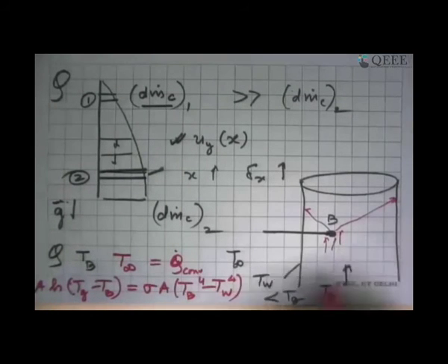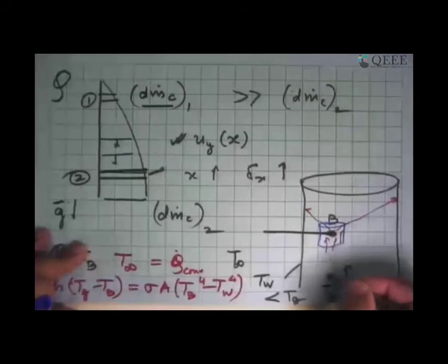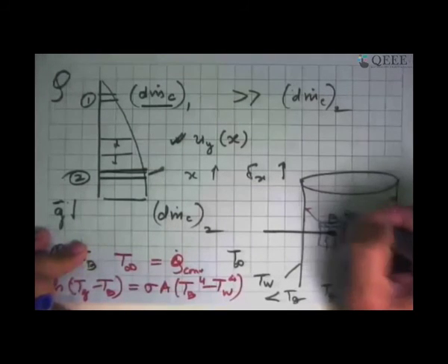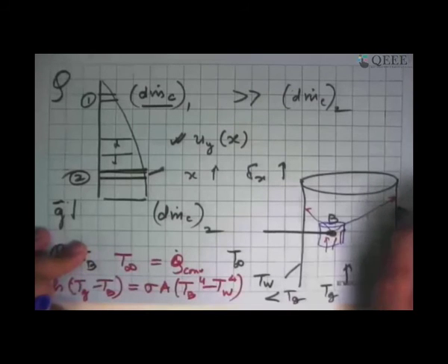This is the problem. So what one can do is we'll enclose this in a small foil. So I do not impede the flow of gas in this, but now this bead does not see the wall, but it sees the foil. And foil is also getting gas over it, and its temperature will not be as low as the bead because this is going to be radiating to the wall also.